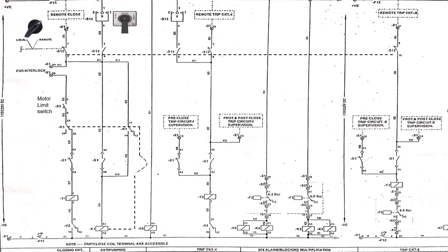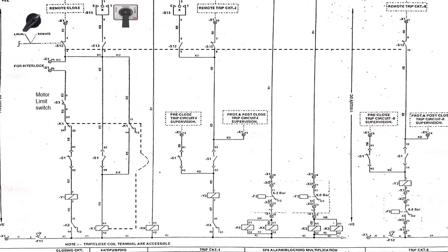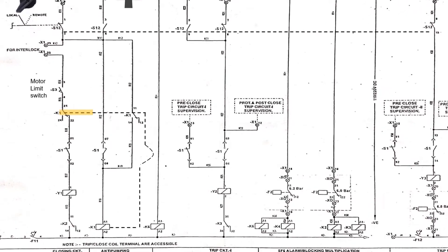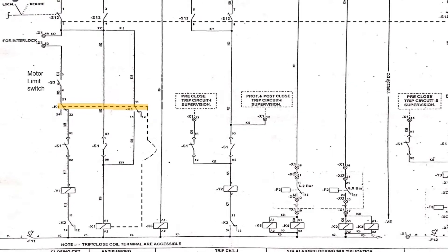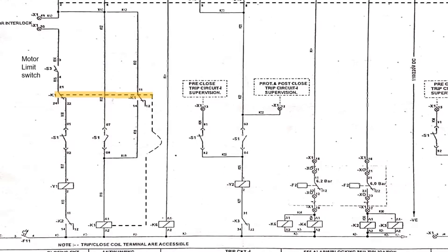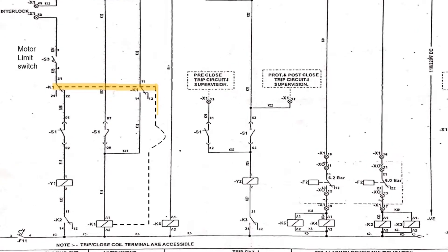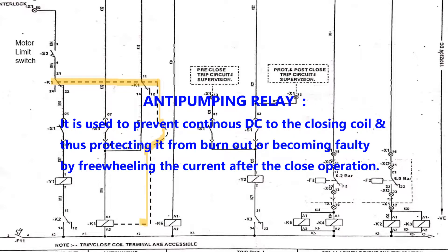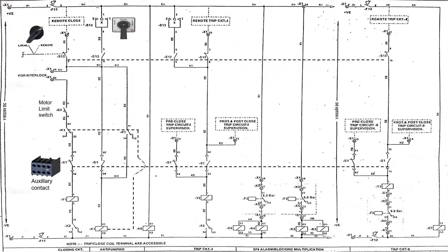Moving down we will see K1, which is an anti-pumping relay. Contacts of this relay are shown by the dotted line — whenever the relay is energized, it will change its contacts: NO will turn into NC and NC will turn into NO. The function of the anti-pumping relay is to prevent continuous DC to the closing coil, thereby protecting it from burning out or becoming faulty by freewheeling the current after the close operation.